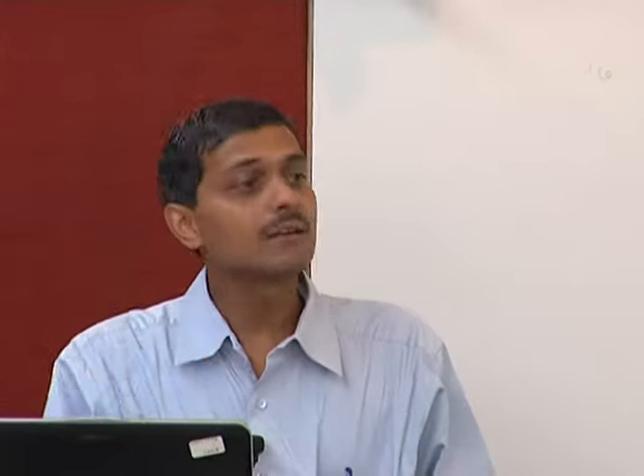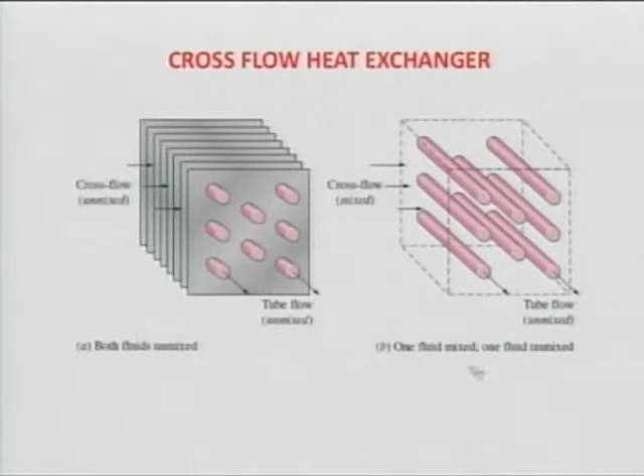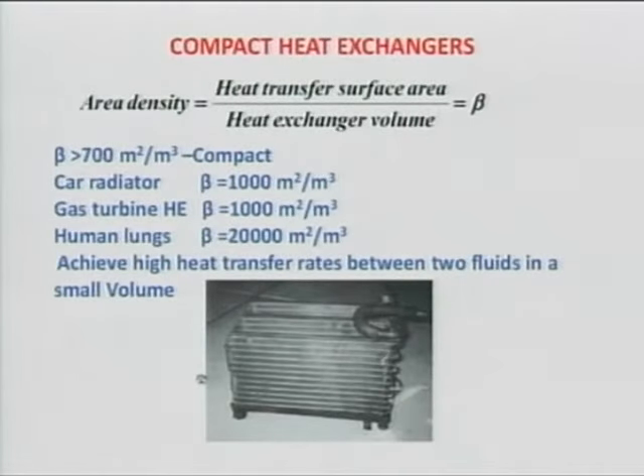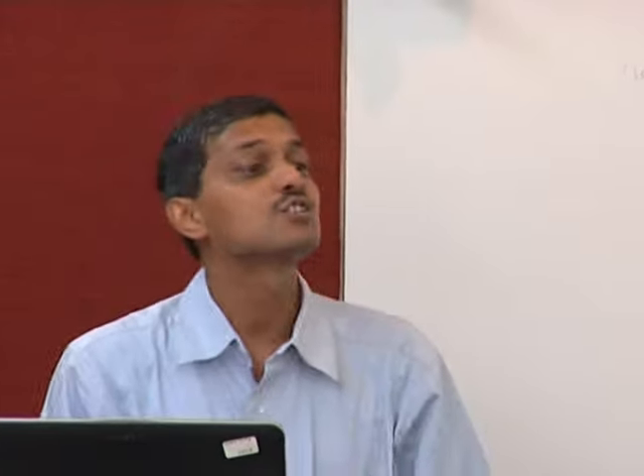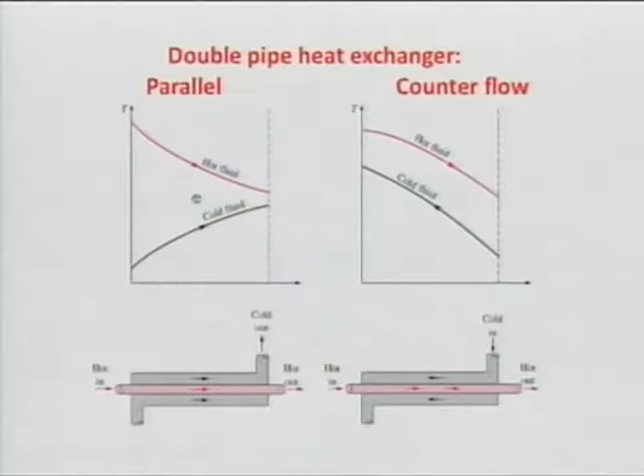In spite of taking multiple passes, there is a limitation. Then you go for other configurations. I said 6 to 10 kilowatts is just a gross number — we can always go for a tube-in-tube heat exchanger if we have more space, but I can make the heat exchanger smaller by going for a shell-and-tube heat exchanger. That is why we usually do not go for larger capacity tube-in-tube heat exchangers. This is the point we need to emphasize to students.